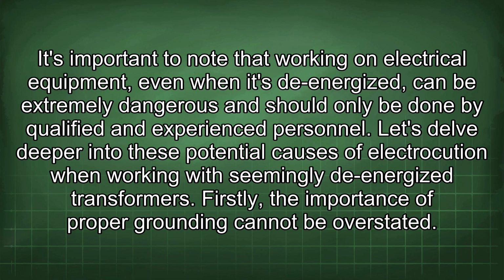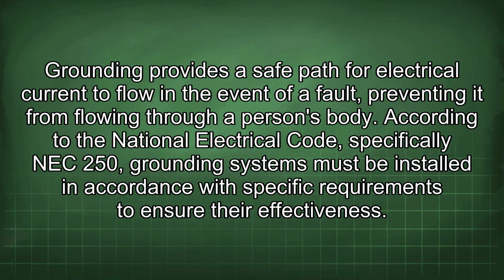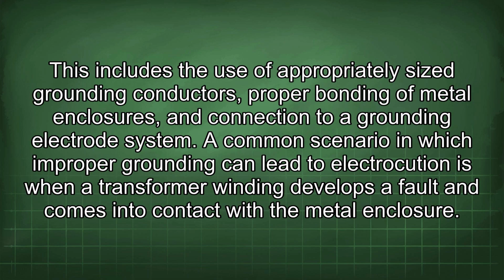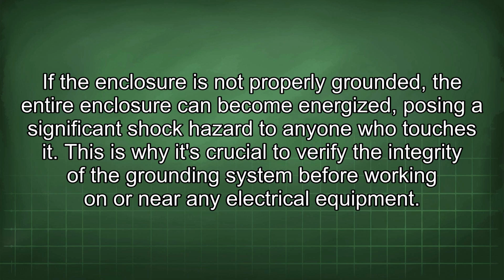Firstly, the importance of proper grounding cannot be overstated. Grounding provides a safe path for electrical current to flow in the event of a fault, preventing it from flowing through a person's body. According to the National Electrical Code, specifically NEC 250, grounding systems must be installed in accordance with specific requirements to ensure their effectiveness. This includes the use of appropriately sized grounding conductors, proper bonding of metal enclosures, and connection to a grounding electrode system. A common scenario in which improper grounding can lead to electrocution is when a transformer winding develops a fault and comes into contact with the metal enclosure. If the enclosure is not properly grounded, the entire enclosure can become energized, posing a significant shock hazard to anyone who touches it. This is why it's crucial to verify the integrity of the grounding system before working on or near any electrical equipment.